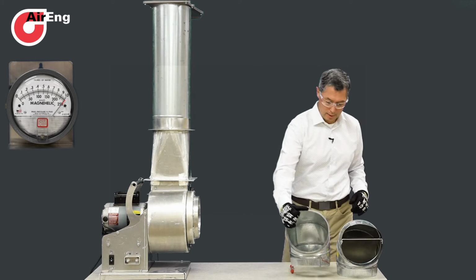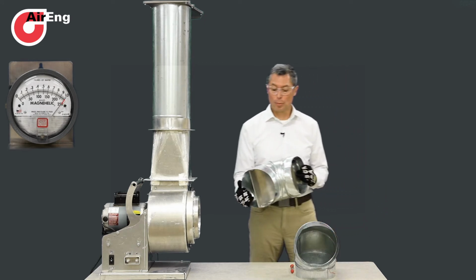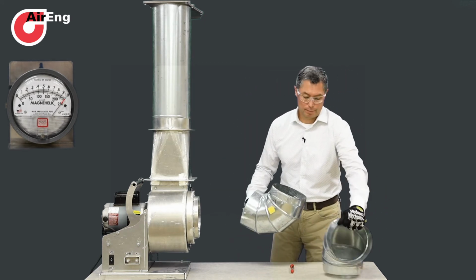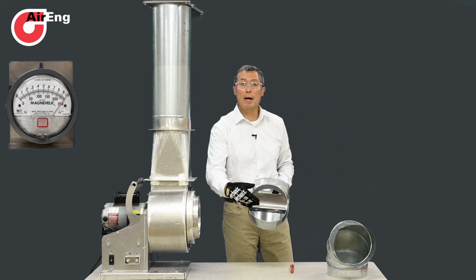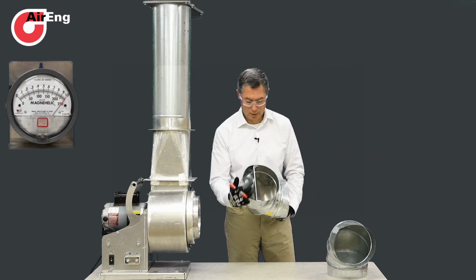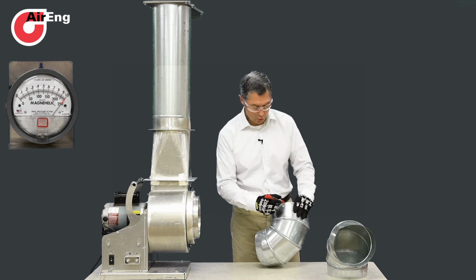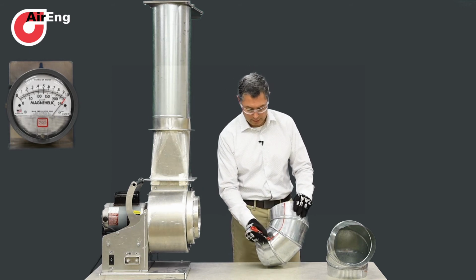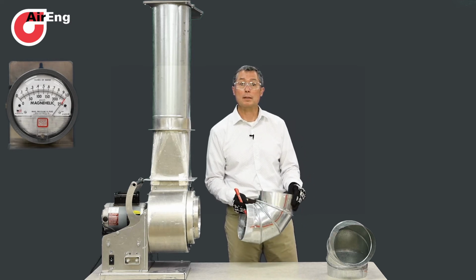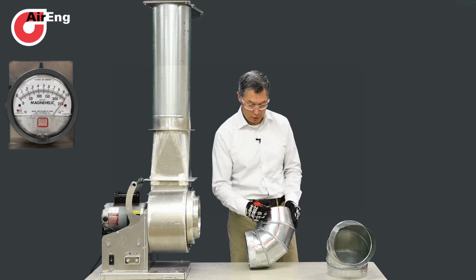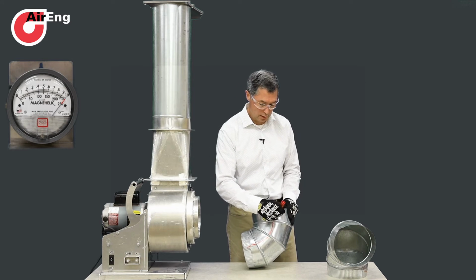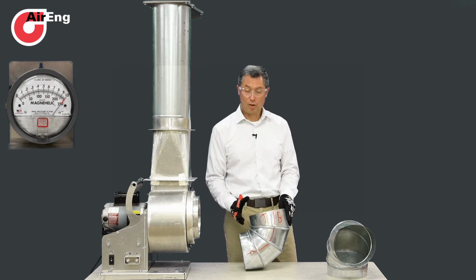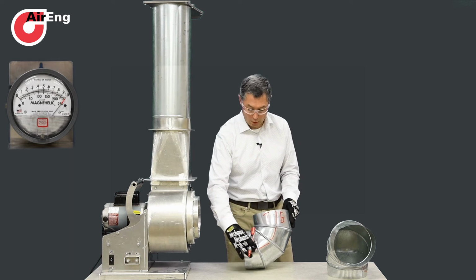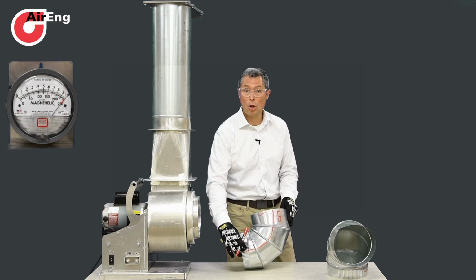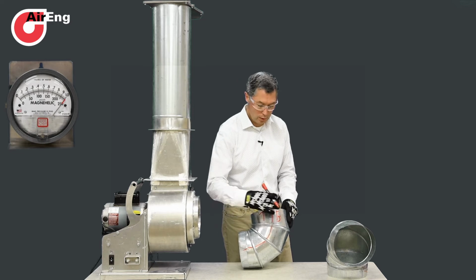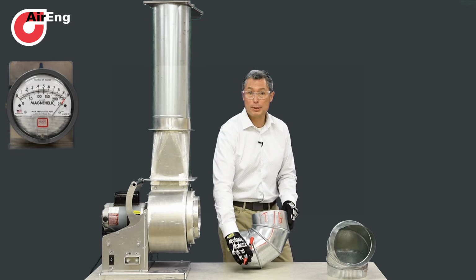We can correct that by breaking the section of ductwork into multiple pieces. Here we have a single vane, which cuts the duct in half. The vane bends like this, so now we have a top section of the duct and a bottom section of the duct. That functionally breaks it into two - air bends along here, so we can now load the mid-top section of the fan wheel, and air comes in here to load the bottom section of the fan wheel.